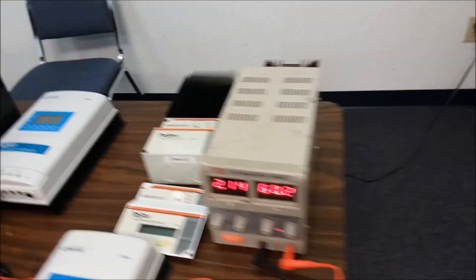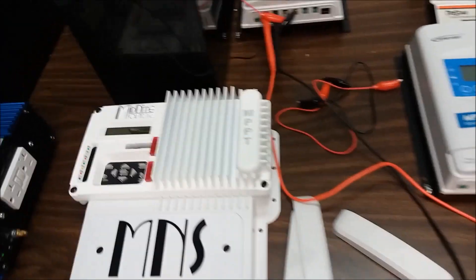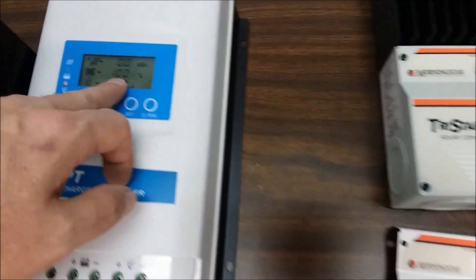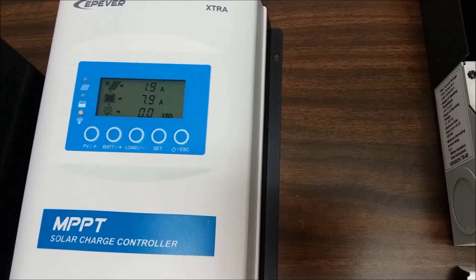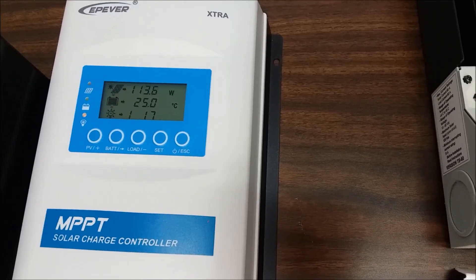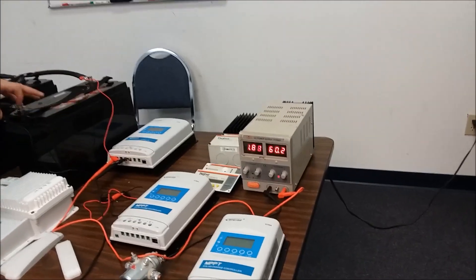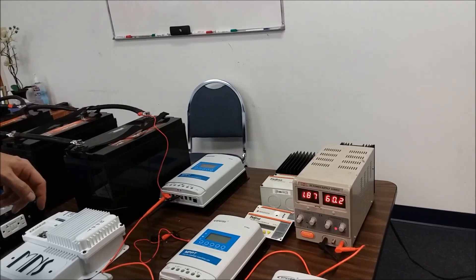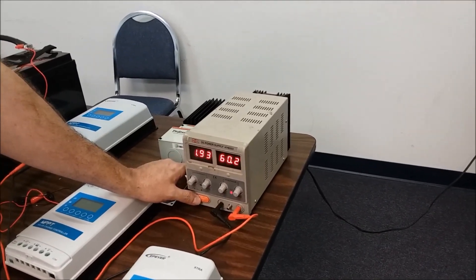We've got that one. The MidNite Kid, made in the USA, this is a nice controller. I'm gonna change over and we're gonna emulate some MPPT solar charging into the system. We'll do that in a moment. But we get back here to the battery. We just pulled that heavy draw and we're showing the system is back up to 100 percent on the batteries. I've been pretty impressed with the testing we've done on these new Tracers. We're gonna throw the Kid on here and see what happens in a moment. This wire is getting real hot, so remember six-gauge wire at least. Remember to take your voltage runs and put them in the voltage drop calculator so you don't overheat things. That's how you cause fires. I'm gonna shut this thing down a minute.